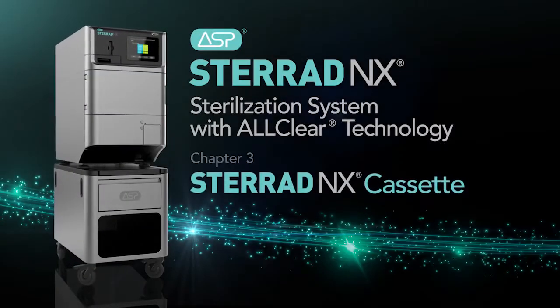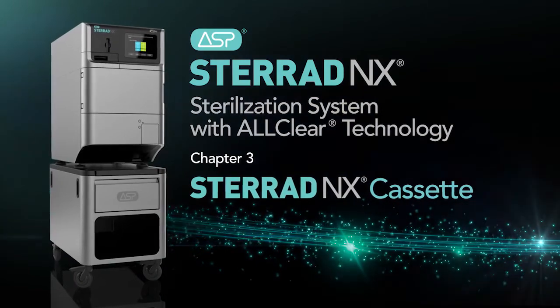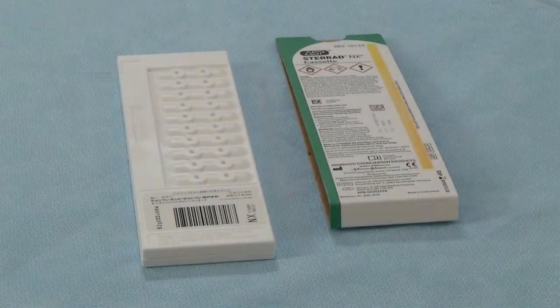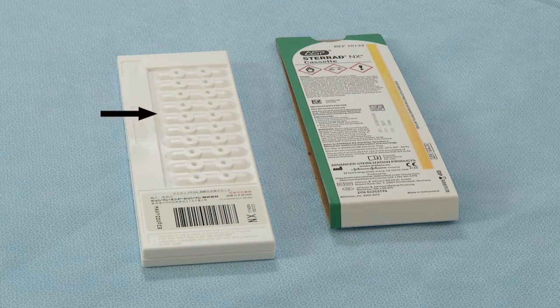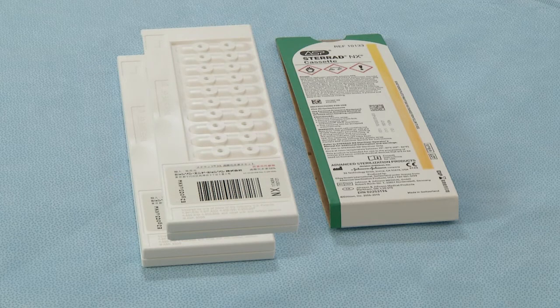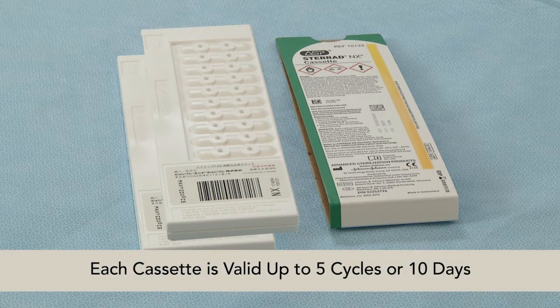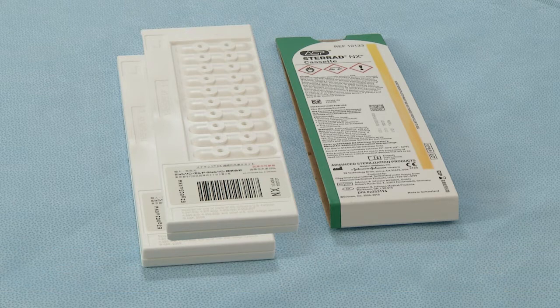Let's discuss the sterilant cassette that is used in the STERRAD NX sterilizer with ALLClear. The cassette contains 10 sealed capsules of 58% hydrogen peroxide solution. There are 2 cassettes per case. Each cassette is valid for up to 5 cycles or 10 days. The use of the cassette in the STERRAD NX sterilizer is controlled by a printed barcode. The barcode limits the use of a cassette to the appropriate sterilizer and ensures cassettes are not used beyond their 12-month shelf life. A serial number on the barcode uniquely identifies each cassette.